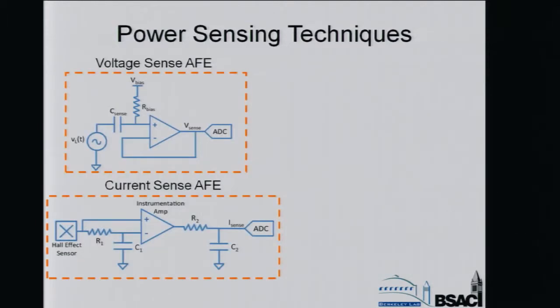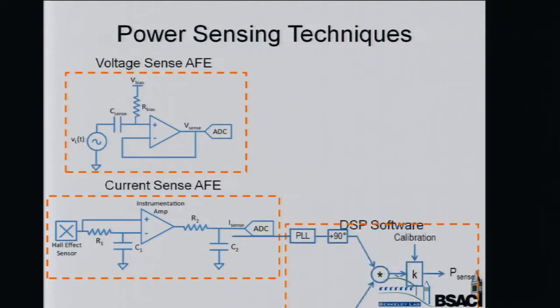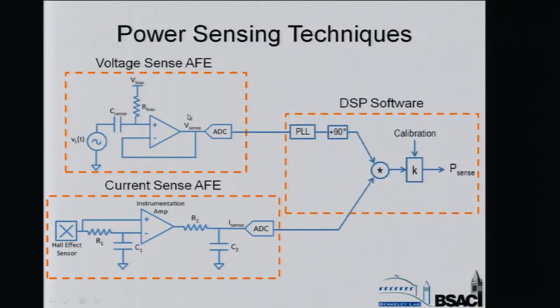Okay, so now we have iSense and Vsense. How do we calculate power? As I mentioned, the Vsense signal is proportional to the derivative of the circuit breaker line voltage. So to account for that, we built a PLL in software, which tracks the phase of this Vsense signal. It phase locks to it and then shifts by 90 degrees. The output of the phase shift is then multiplied by the iSense signal, and the output of that multiplication is scaled by a calibration factor K, which I will describe in more detail later. The result of that scaling is then real power in watts.